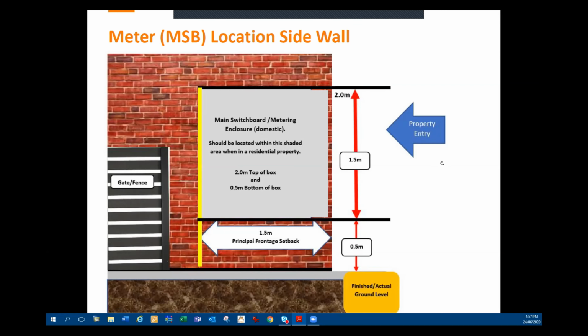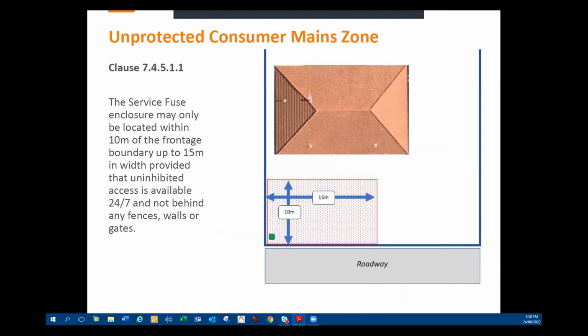For unprotected consumer mains zone, we've had some issues, especially for larger properties where the pit, pillar or transformer might be right in the front corner, but the house or building might be set back a lot further than the 10 metres. So we've tried to give it an indication that will allow the service fuse enclosure within 10 metres of the boundary and up to 15 metres in width, because we've had some properties that have been 50, 60 metres wide and had the building built on the other side of the property.